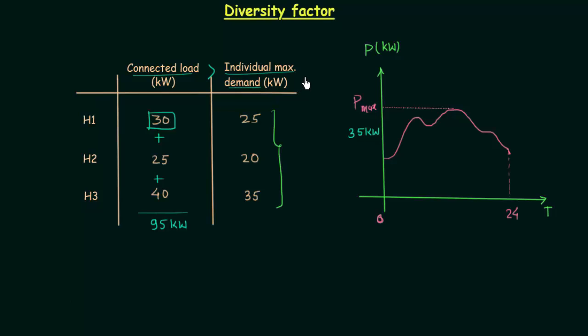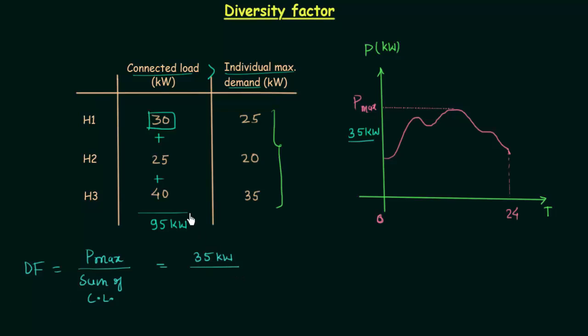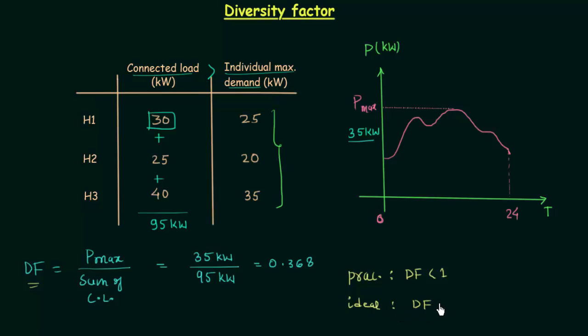In the previous lecture we saw what demand factor is and we also calculated it for this particular case. The demand factor is equal to the ratio of maximum power demand Pmax to the sum of connected load. In this case, the maximum power demand is equal to 35 kilowatts and the sum of connected load is 95 kilowatts, giving a demand factor of 0.368. In practical cases, demand factor is always less than 1, and in ideal cases it is equal to 1.